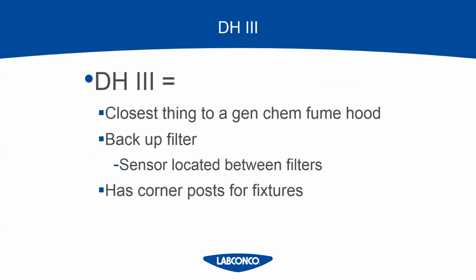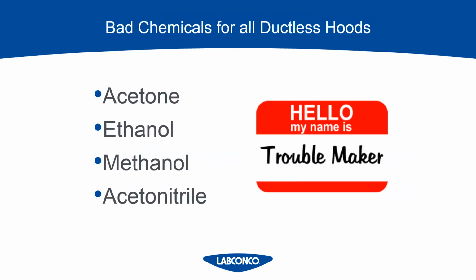It has a sensor located between the filters, so you have a full backup filter, and it does have the corner posts for fixtures, just like a general chemistry hood. Something that applies to all of the types of ductless hoods that we just learned about is that there are some bad actors when it comes to chemical compatibility with carbon filters. And they aren't ones that are considered extremely hazardous, because a lot of times when I get phone calls about, "I'd like to go ductless, I'm not working with anything too terrible," I say sometimes that's not even a concern, because some chemicals that people work with on an open bench actually provide the problem.